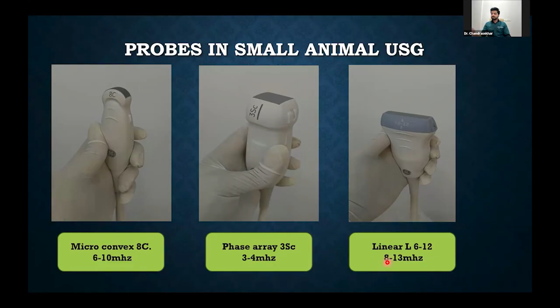So I just want to let you know how the USG works. Basically, this USG works on the piezoelectric effect. The principle itself is the piezoelectric effect. To be very simple, we send a wave through a tissue, and this wave hits a particular point and comes back. Whenever it comes back, it returns to the same point from which we are emitting the waves, and from there it is converted into an electric signal, and the sound waves are formed. Ultrasound is actually a high frequency sound of more than 20 kilohertz. But for veterinary use, we use a frequency between 2 to 15 megahertz.